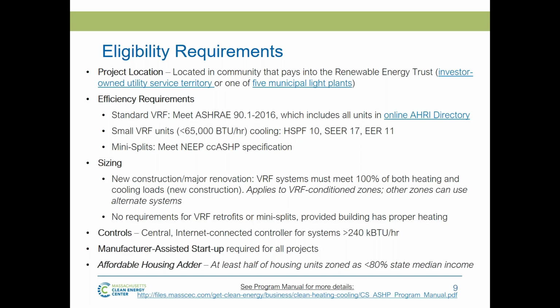In terms of efficiency requirements for the units that are being installed, for standard VRF systems, that's any system above 65,000 BTU per hour of capacity. They're tested under AHRI 1230, and they need to meet the current ASHRAE commercial code, basically. That's ASHRAE 90.1-2016. All units that meet that code should be listed in the online AHRI directory, and you can download the specification sheets there and check that the units qualify.